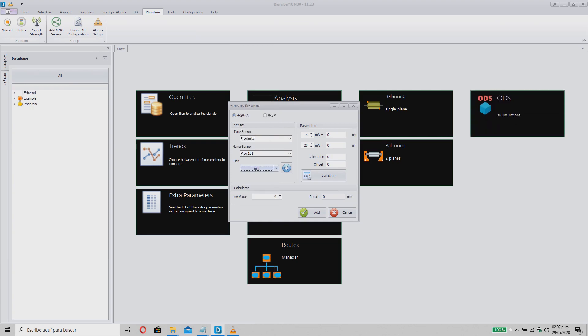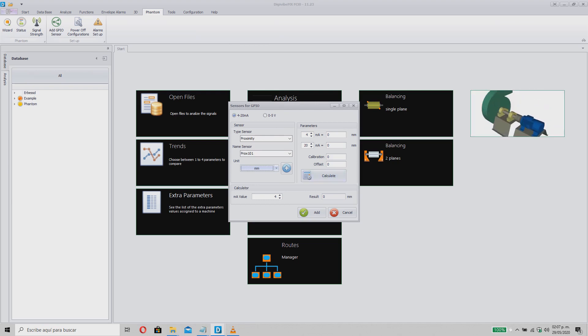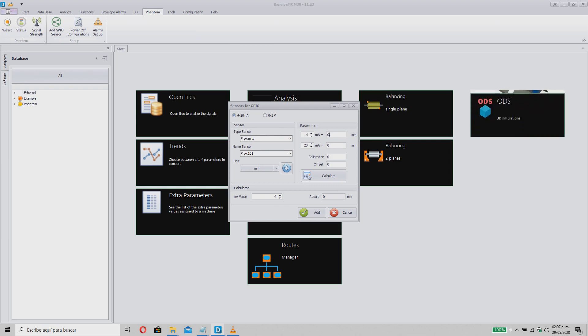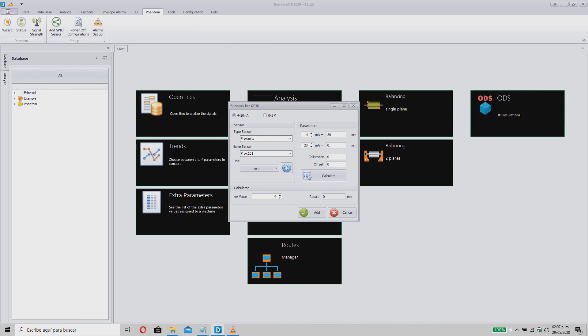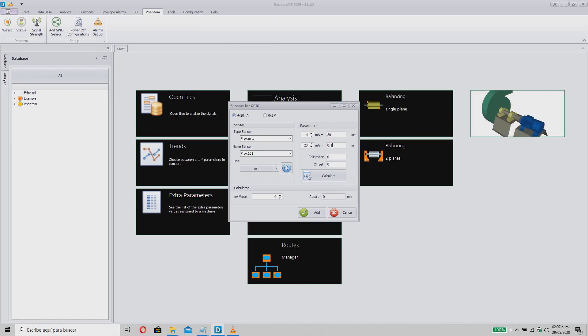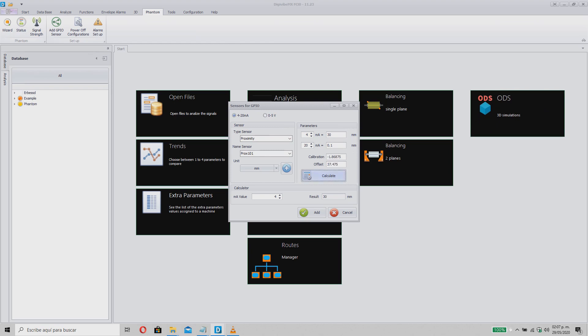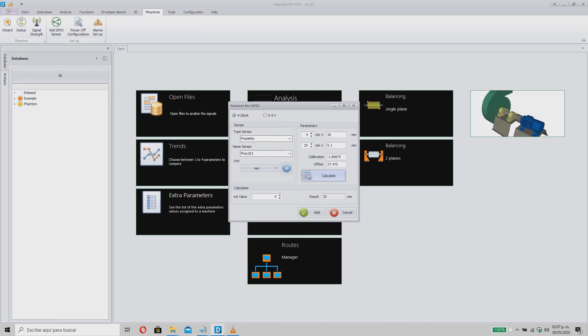Select your unit and modify the values on the right side. These values indicate the meaning of each signal translated to the parameter you are measuring. You can find a conversion table in the operator's manual for your sensor. Otherwise, contact your developer. Once the two values are established, click Calculate to find the calibration value. These values are internal and should not be modified.